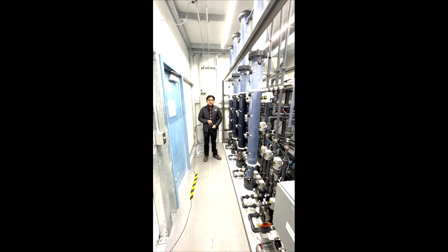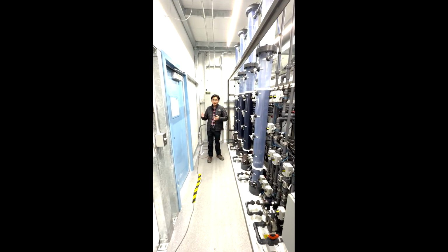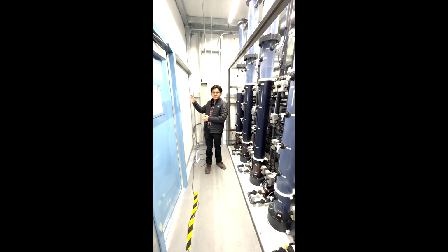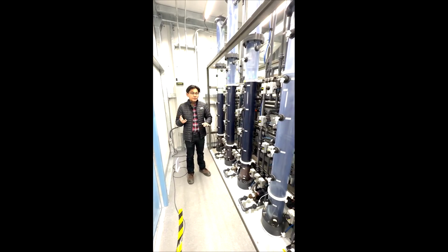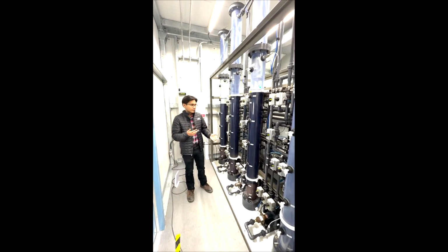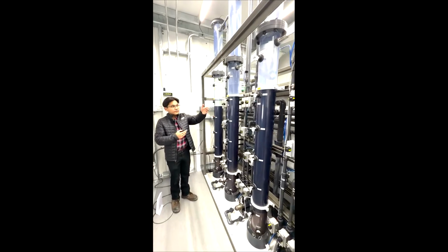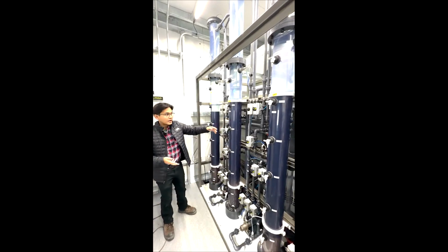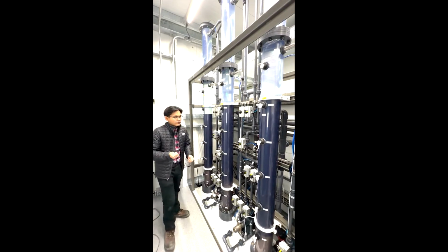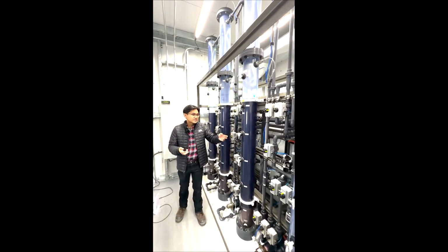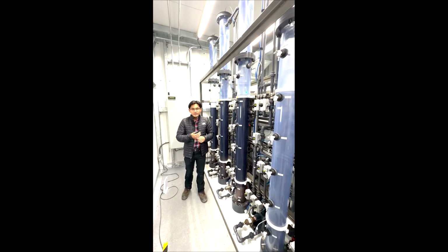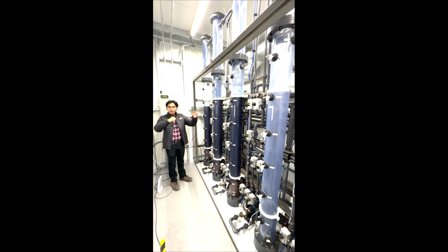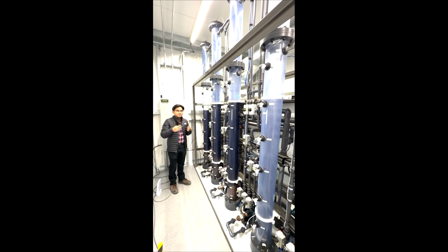And so the second part of our treatment system after it's come there is filtration. And what do these filters do? Well, the first part was mostly for organic materials, but this will target a lot of the metals that are in water. So we have three different filter systems here. We have coal, this is anthracite, just a fancy name for coal. And then we have granular activated carbon. This is actually used in a lot of Brita filters that you'd have in your home. And so this trailer allows us to figure out which of these will be the best option for the town.